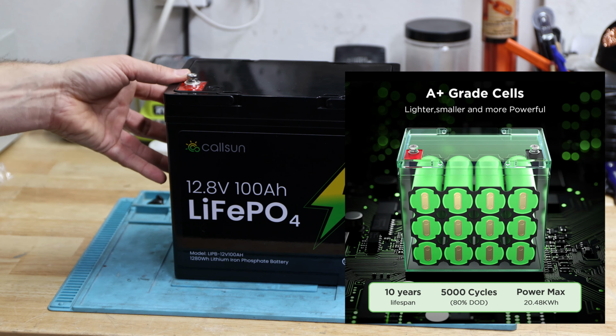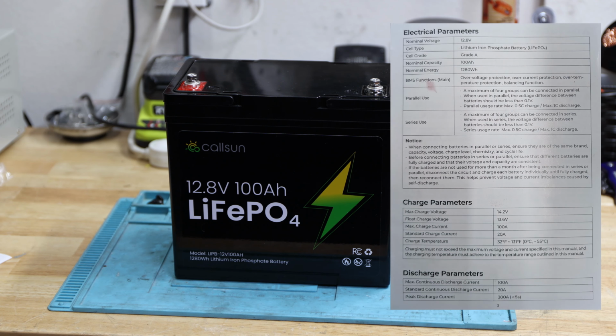I'm looking here on the rear side, and it states nominal capacity 100 amp hour, charge parameters, max charge current 100 amp, and max continuous discharge 100 amp as well. Standard would be 20 amp charge and discharge.